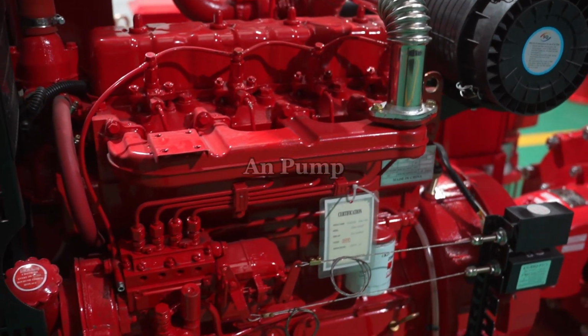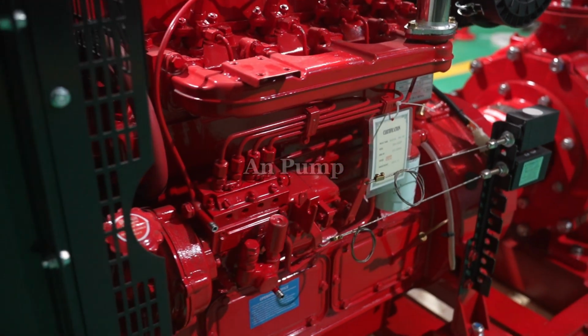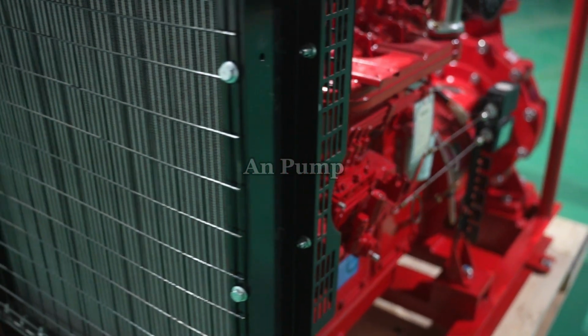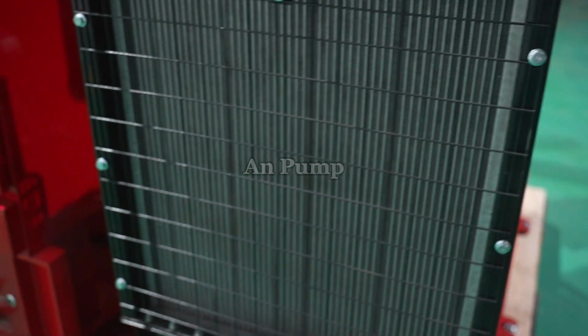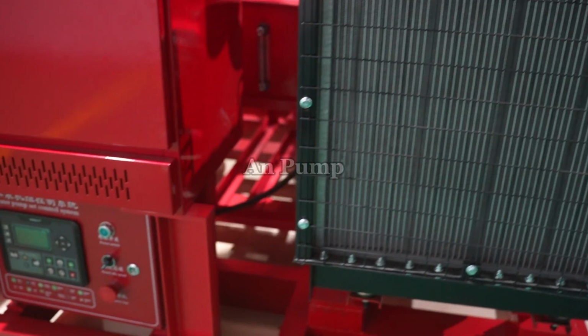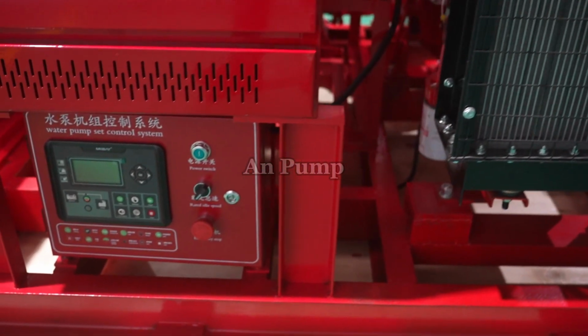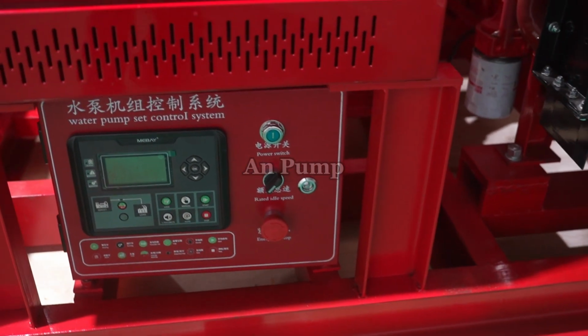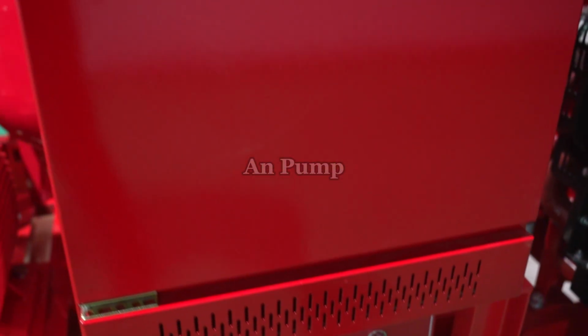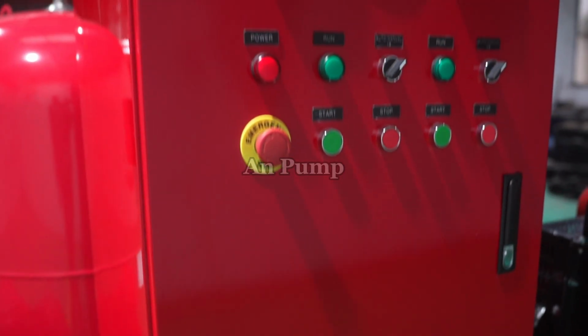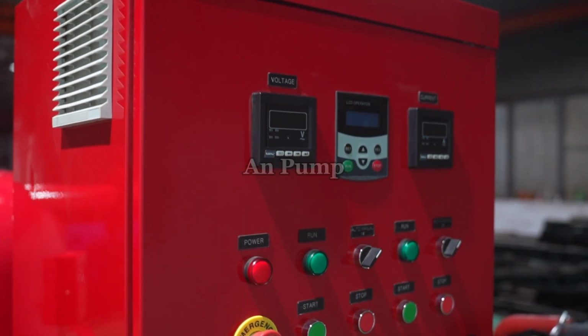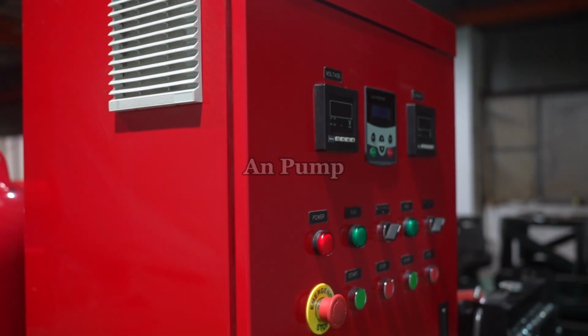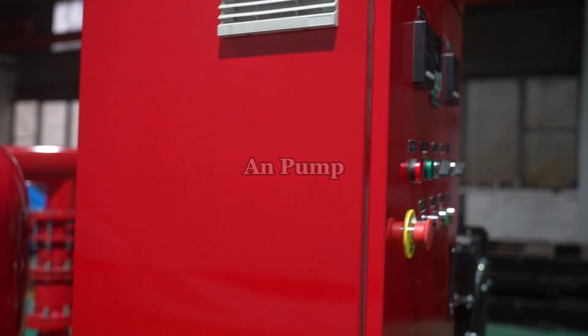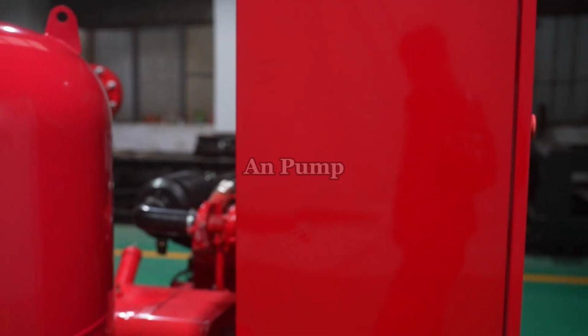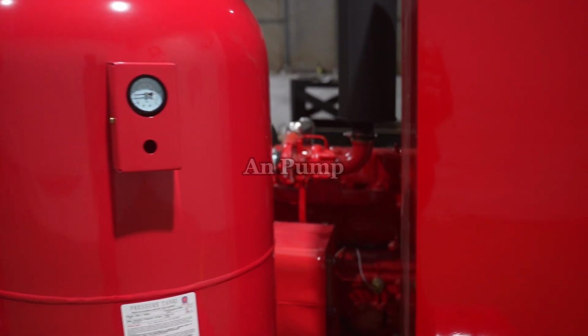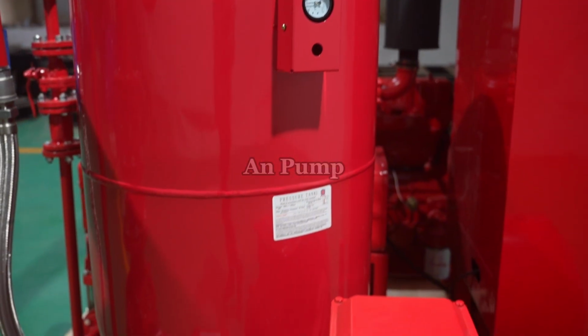Type number 1, the end suction centrifugal pump. This is the most common type you'll see in industrial and commercial buildings. The name tells you how it works. Liquid enters axially from one end, the suction end, and then discharges at a 90-degree angle from the top. The design is simple and cost-effective. One of the best features is called back pullout. That means you can remove the rotating assembly, the impeller, shaft, bearings, and seal, without disconnecting the pipes. That saves a lot of downtime during repairs.